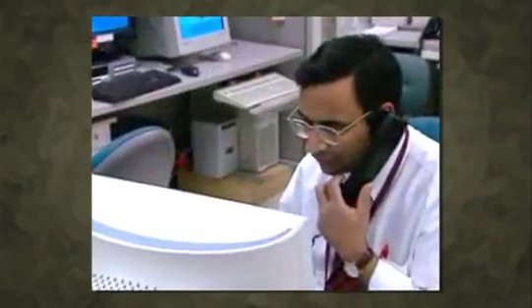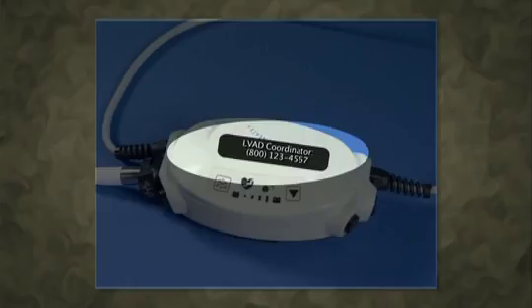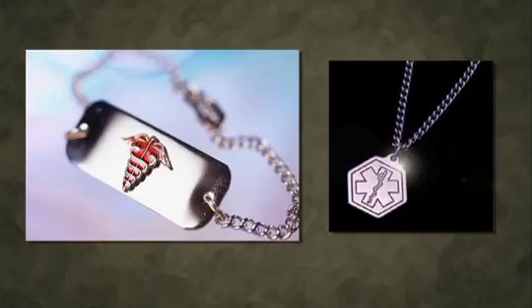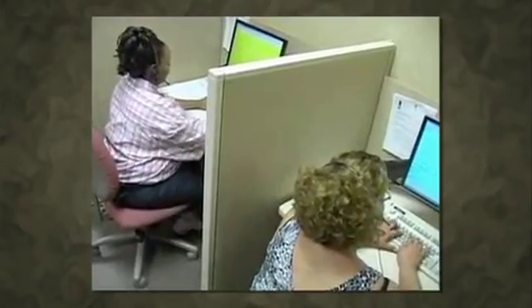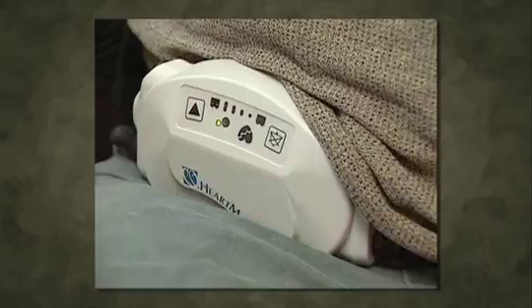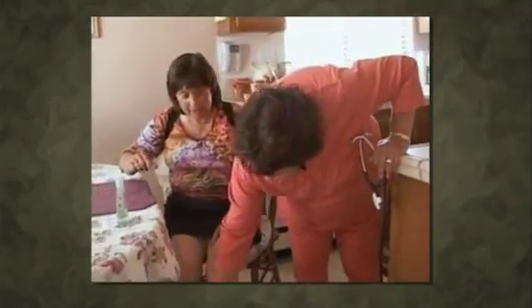Patients and caregivers are trained that in the event of a red heart alarm, they contact 911, but then also contact the patient's hospital immediately to speak to a VAD coordinator. The coordinator may be able to assist in the care of the patient. If you find yourself in a situation where the LVAD coordinator was not contacted, you may contact them yourself. The system controller will have a sticker on it with the contact information of the hospital. The patient should also be wearing a medical alert tag with the number on it as well. When you call the number, make sure to press 0 for the operator, who can then connect you to the LVAD coordinator. If the device is connected to the patient correctly and appears to be receiving power, continue with your assessment of the patient by evaluating their ABCDs as we have previously discussed.